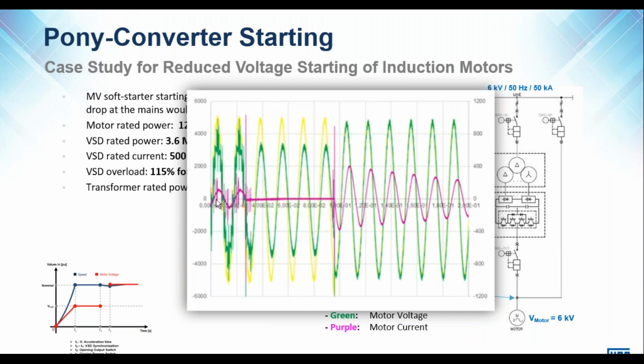And here's an actual measurement of the startup of this machine, and then the bypass from the VSD to the supply. So we can see here, our green graph is the VSD output voltage. The RMS value, although it doesn't look like it, is lower than the yellow graph, which is the supply voltage. And the purple is the motor current. So when we started the motor with the VSD, we ramped it up to full speed, and this is the output voltage.